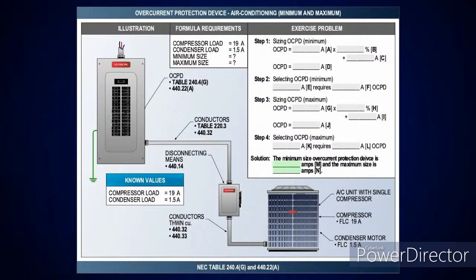And in here, you've got a compressor of 19 amps and 1.5. You should automatically learn this. I'm going to go to 440.22A. I'm going to take it at 175 percent. If I need to do a maximum, it's 225%. Okay? Right. And then if they just say next size and they're doing the 2023 code, then you would do the minimum and just go up to the next size overcurrent device.